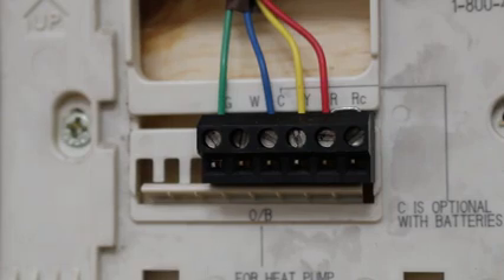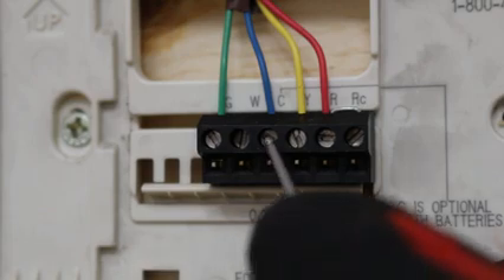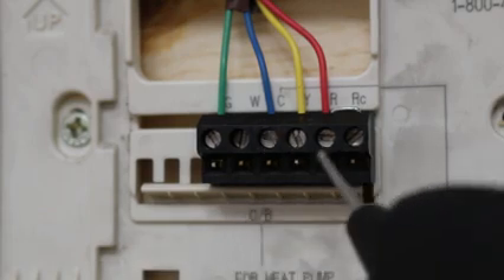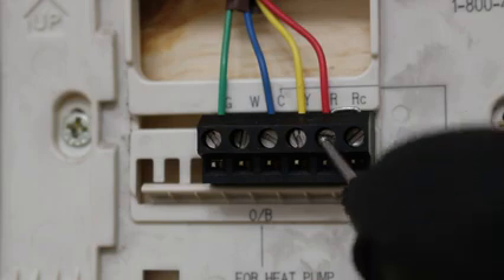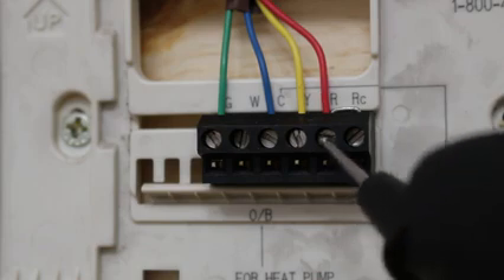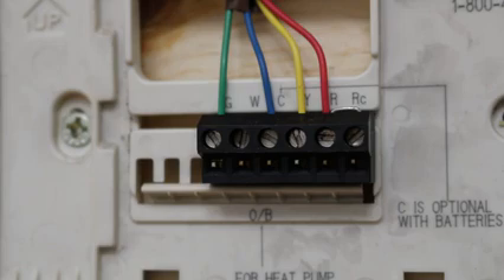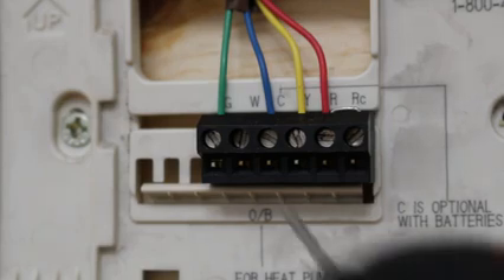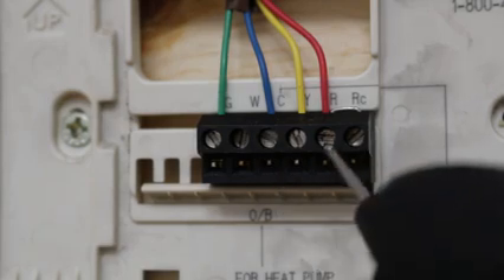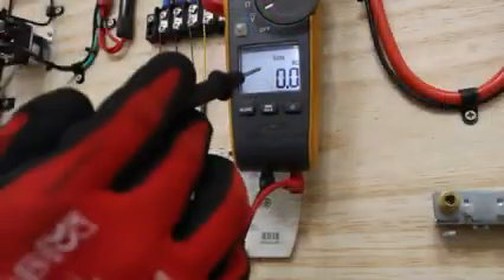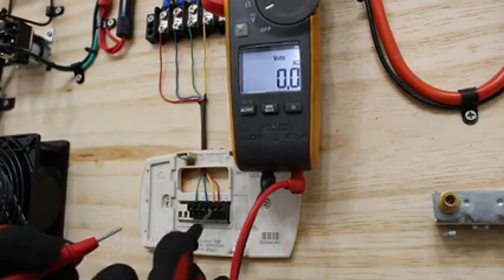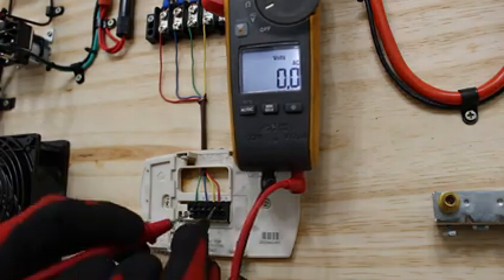at your thermostat. Your C wire stands for common, and your R stands for your 24 volts, your power wire. And this is all coming directly from your transformer. So between R and C, you should have 24 volts. I have my multimeter set to volts AC, and we're simply going to check between R and C.